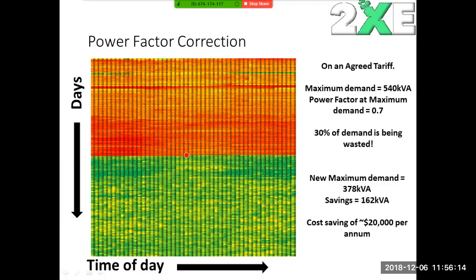So this winery made a saving of 162 kVA, which was approximately $20,000 saving per annum. So by installing power factor correction, this winery made a saving of $20,000 per annum. Now, a couple of important things to note is that the unit itself cost around $20,000 to install, so it had a payback period of about a year. So it's quite a good investment, or a very, very good investment actually.